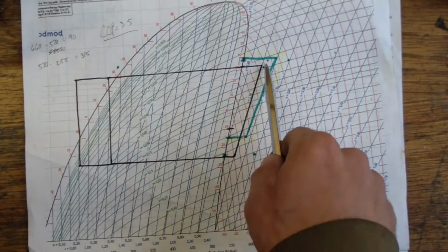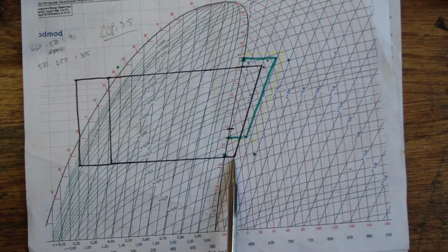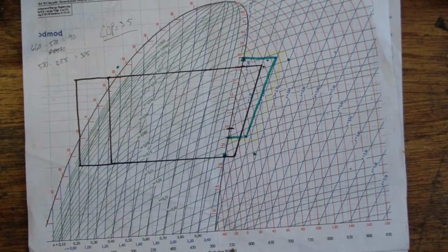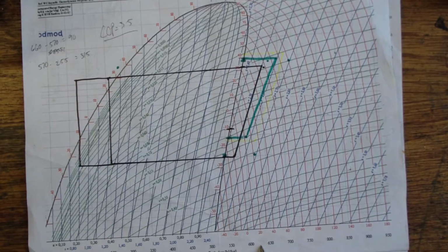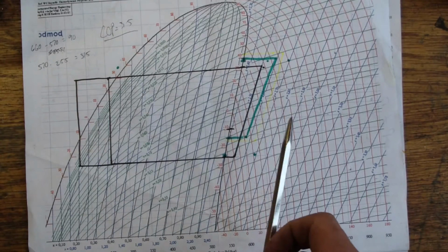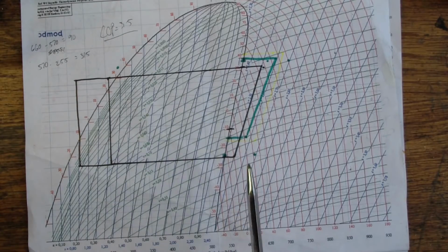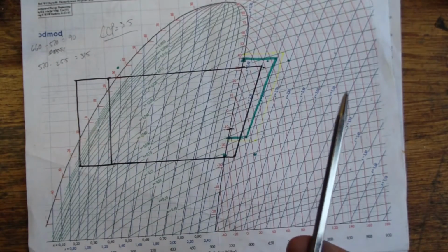Likewise, we can look at the compressor itself. At the inlet of the compressor, it was at 560 kilojoules per kilogram, and at the exit, it was at 630. We can look at the difference between those two. The amount of heat added during compression is essentially the same thing as the amount of work being done. If your electric compressor were 100% efficient, you should actually be able to determine the mass flow rate through the system, but your compressor is not 100% efficient.